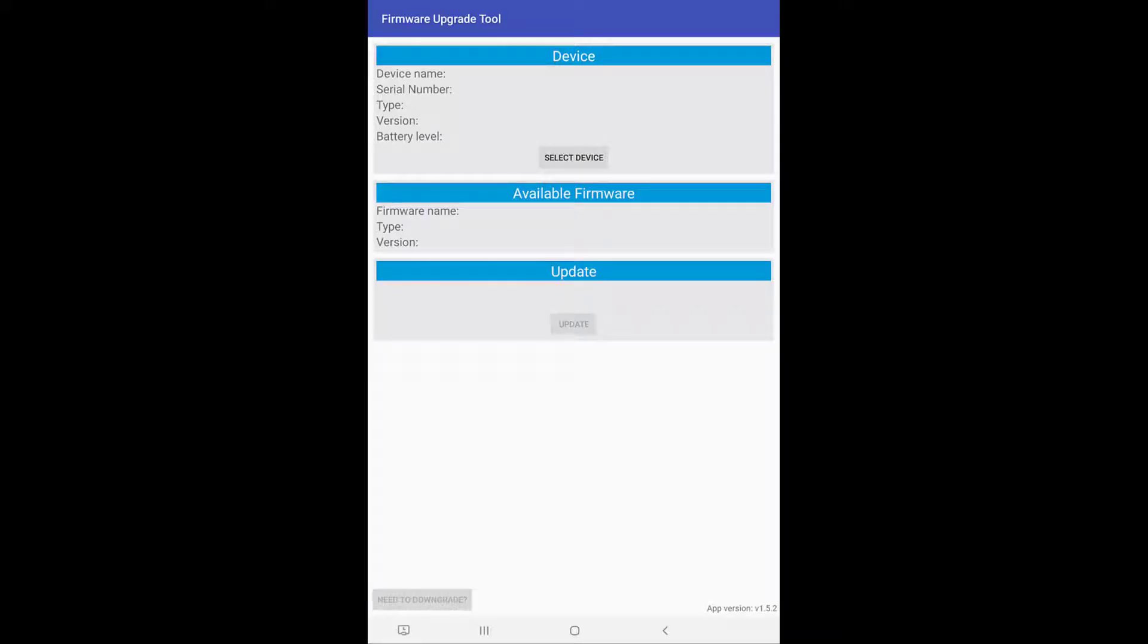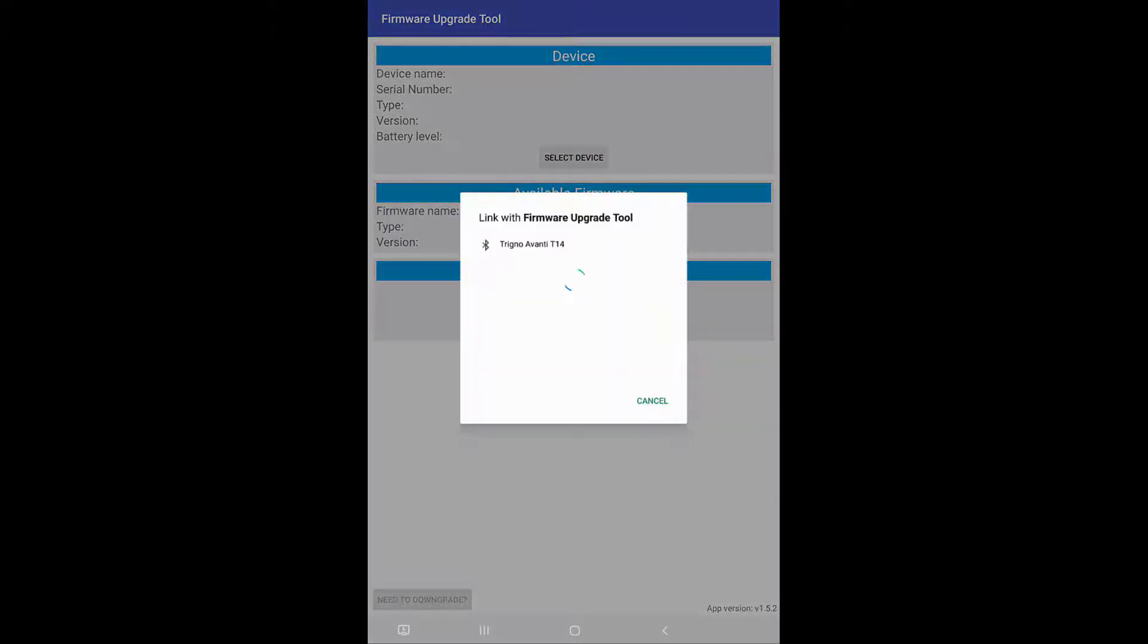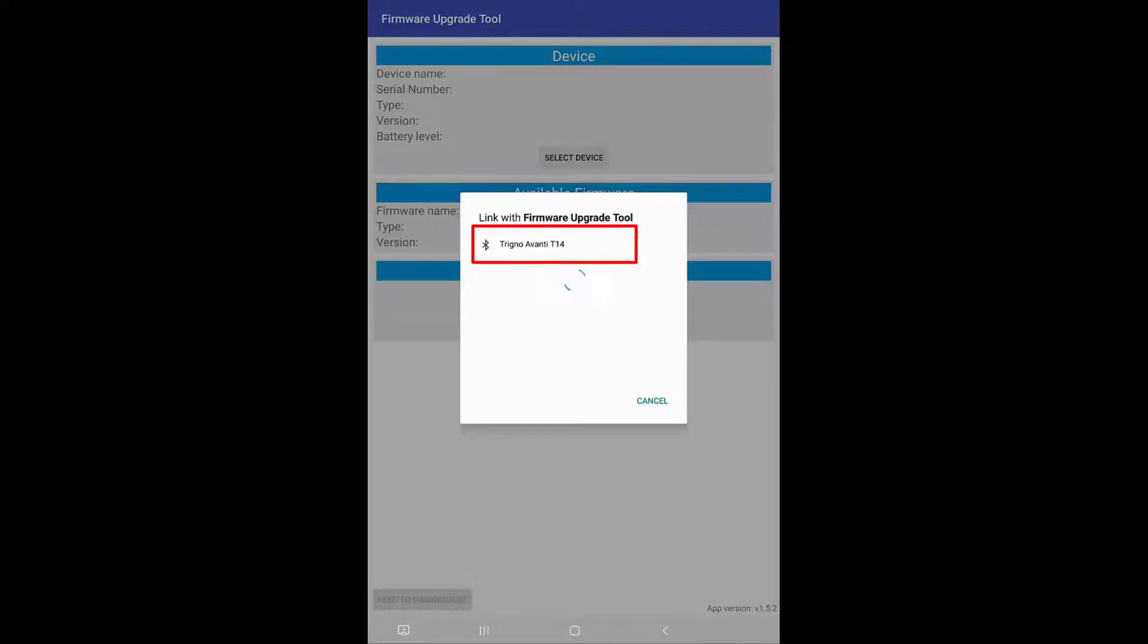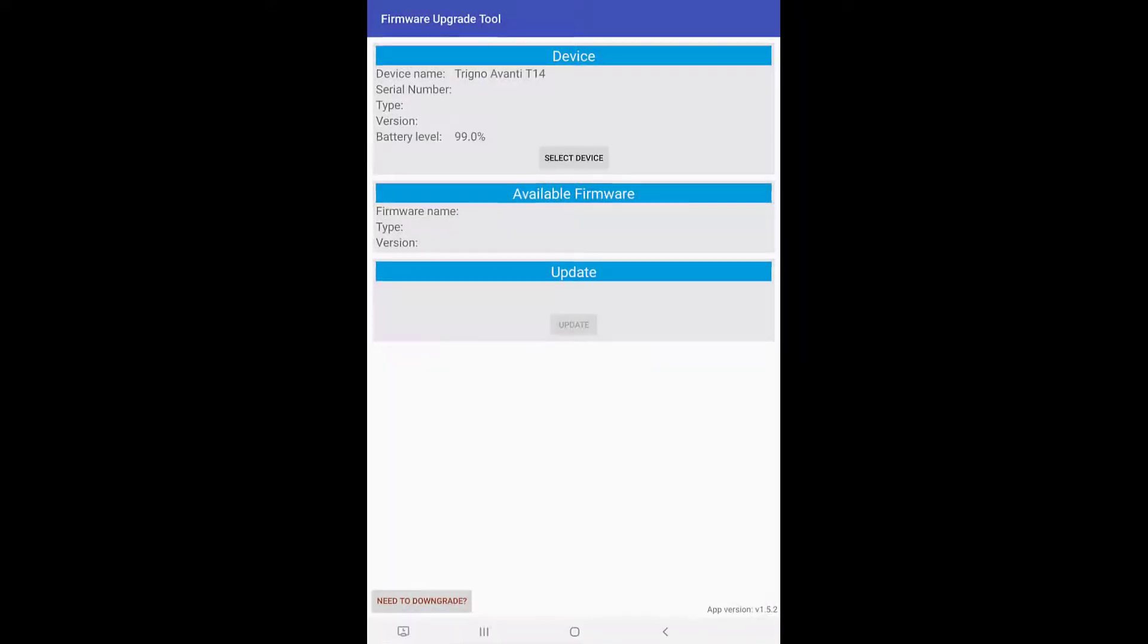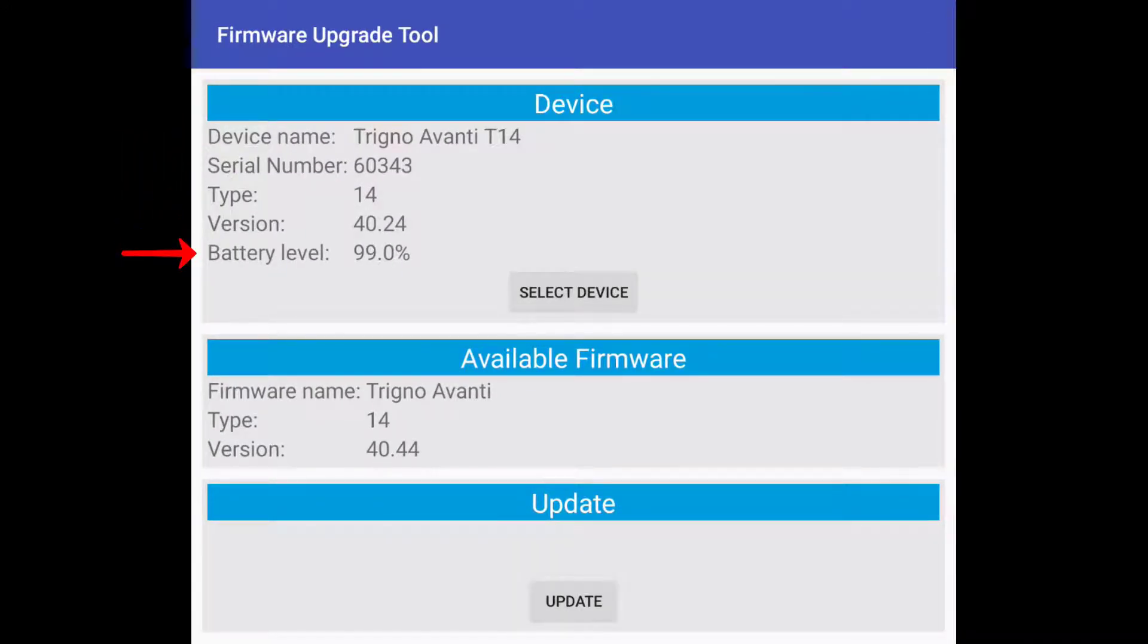Next, click on the select device button near the top of the screen. Make sure Bluetooth settings are on and location services are enabled for the app. Select the sensor intended for the update. The sensor name, serial number, firmware version, and other information will show on screen.